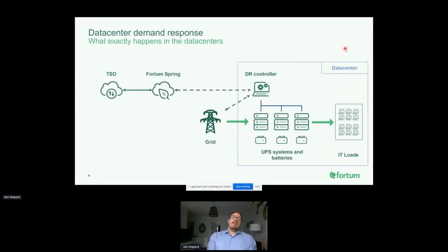When a data center joins us, we install a controller unit, connect to the UPS systems, and connect to the grid to measure it. We're also connected through the transmission system operators, and through the Fortum Spring platform we market this capacity.